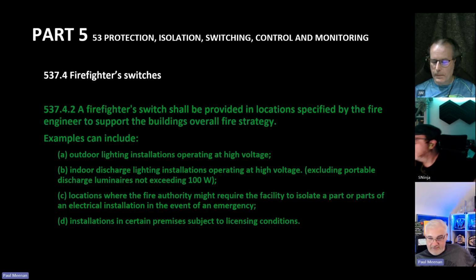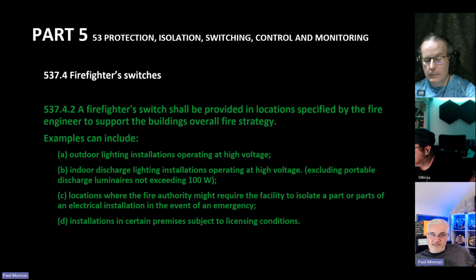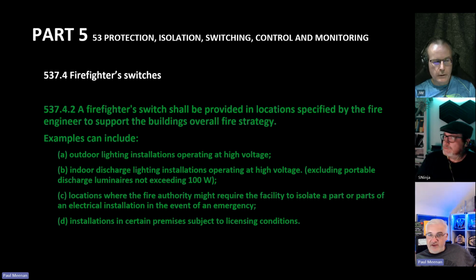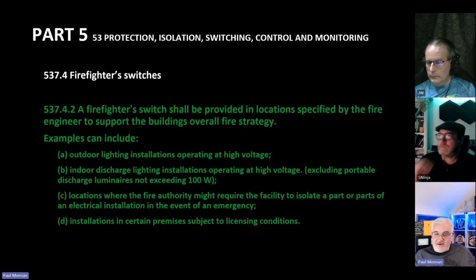That's quite costly and space consuming. So this is going to be an interesting one to track as far as how it impacts, because I don't disagree, by the way, with a firefighter switch. For instance, on buildings where there's solar PV, the fire alarm panel, if you're not already, should be wired to tell the solar inverter to shut down. That way you don't have live energy still being generated from a solar system in a building that's supposed to be dead. So there's lots of considerations we need to take now to protect firefighters electrically as well that may not have been considered sufficiently.